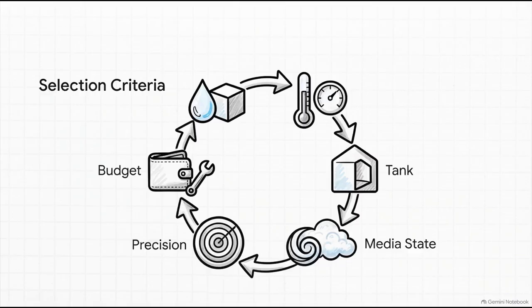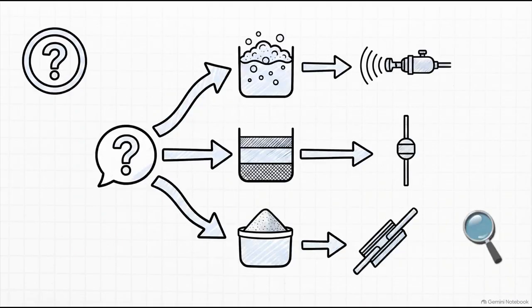Then, they balance the strict accuracy required against whether they want a contact or non-contact instrument, all while keeping the ever-present constraints of budget and long-term maintenance in mind. Ultimately, it's all about matching the unique physics of the sensor to the specific problem. Here's how that plays out in practice. If you've got foamy or vaporous materials that mess with sound waves, you go with guided wave radar or standard radar. If you need to measure the exact interface, the point where oil and water separate in the same tank, you'd use a displacer or guided wave radar.